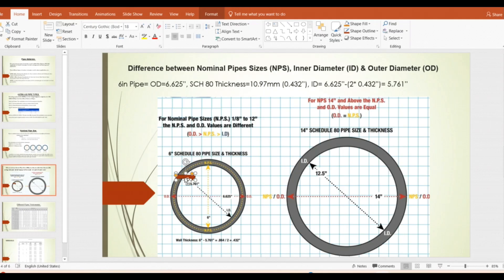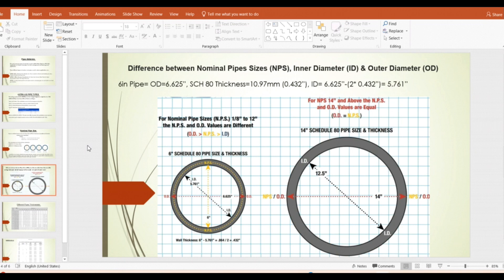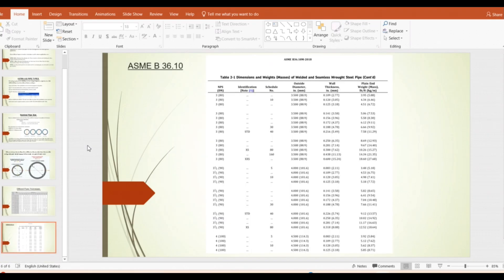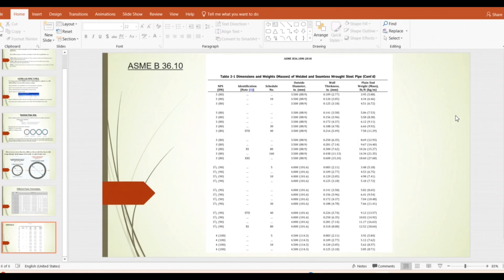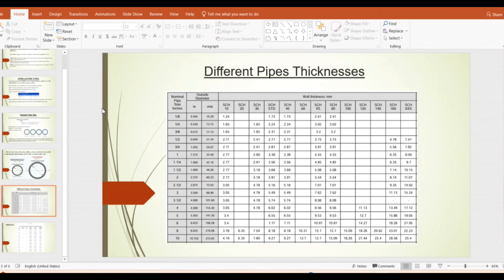So if I say a 4-inch pipe, that 4 inch is the nominal pipe size, but the actual outer and inner diameters will vary based on the schedule being used. The same pipe can be used for oil and gas or for chilled water — the application differs and the schedule differs, so the pipe wall dimensions will differ. In ASME B36.10 for carbon steel, nominal pipe sizes and wall thicknesses for different schedules are all tabulated. This is the basic concept to understand regarding pipe sizing — what pipe we are using, what schedule, and what grade.